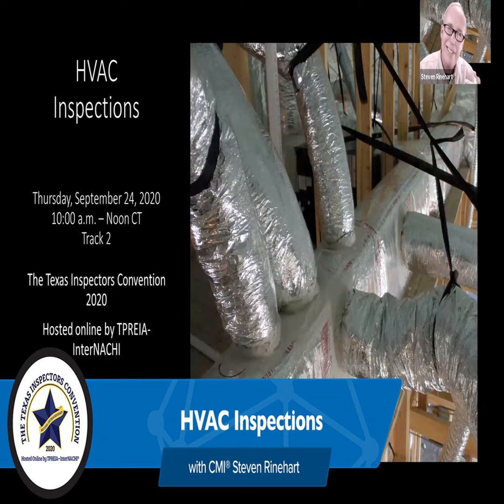Because as far as I know, we don't have sediment screens in the air handler. The belief is it'll just burn anything away, but if you get something very big in your gas line, which you could when they do repairs, open lines. I mean, we do boil notices when we do water lines and they break in the water company, but if the gas line breaks and they redo it, I'm telling you, what gets in that thing blows all the way to the end of yours. And the drip loop is designed to kind of catch it. You figure the centrifugal momentum would carry solid things into the drip loop, and clean air would make the turn and go into the air handler. That can work.